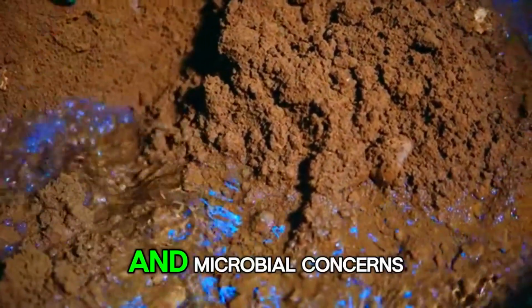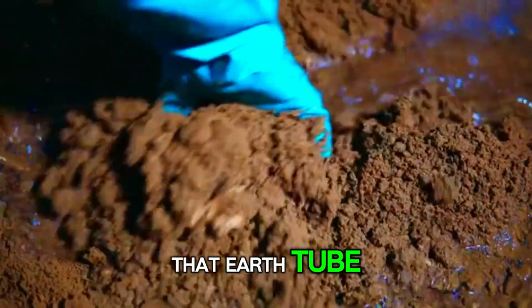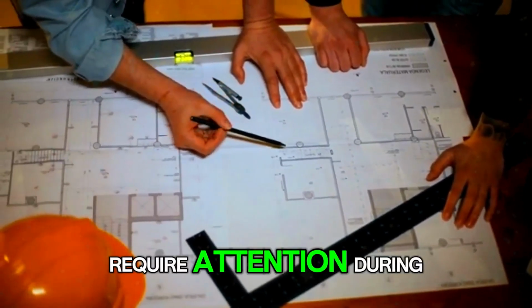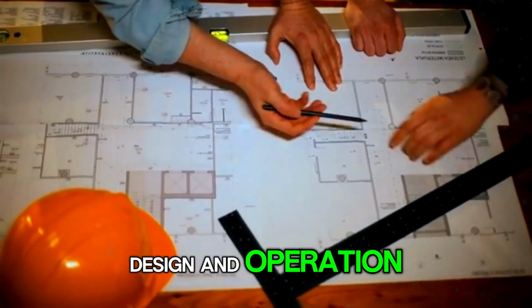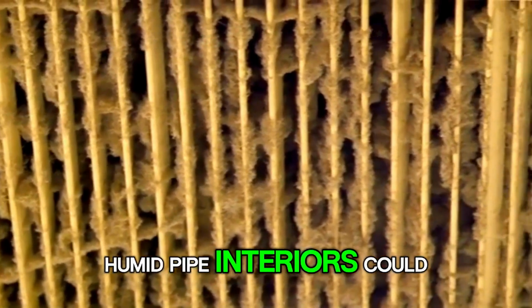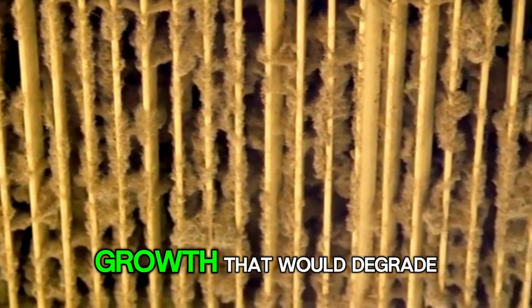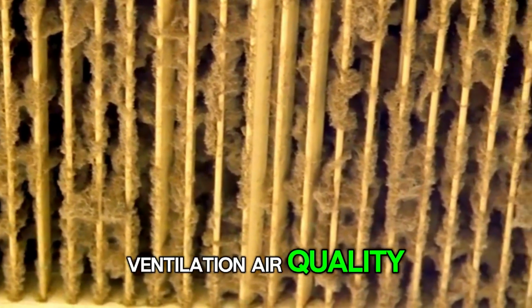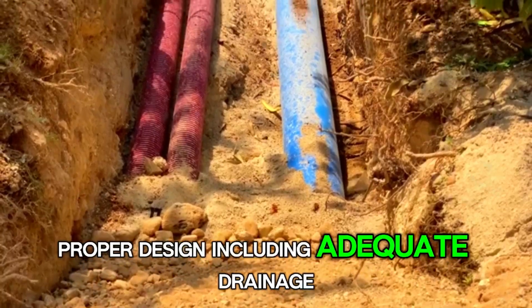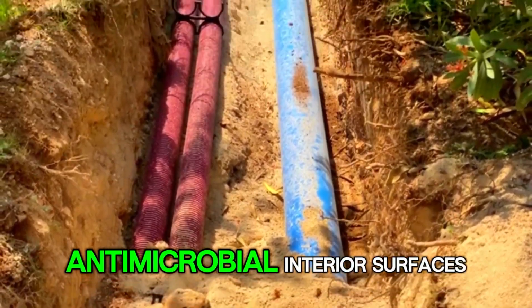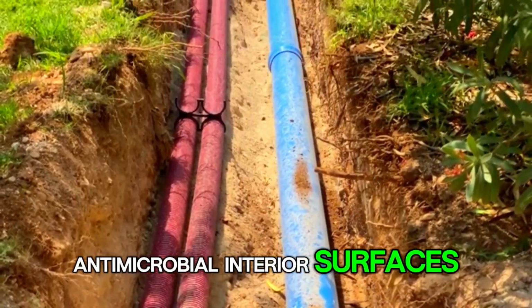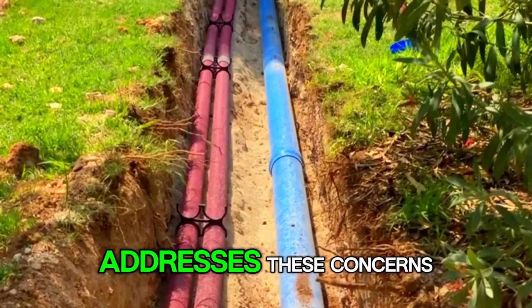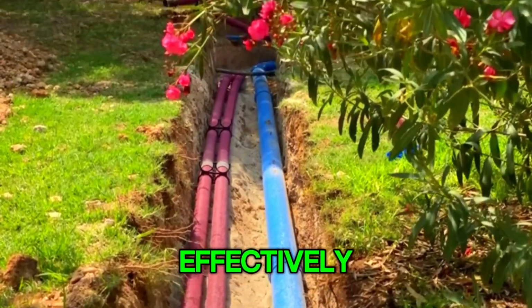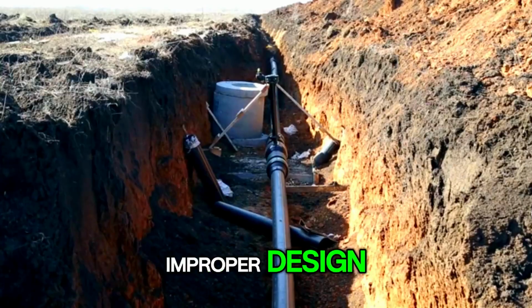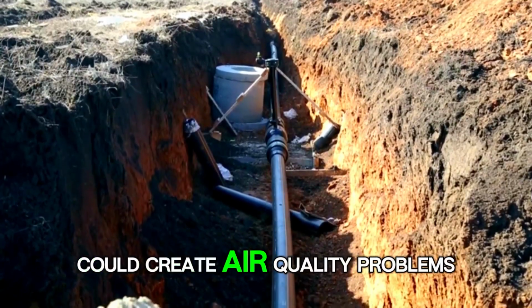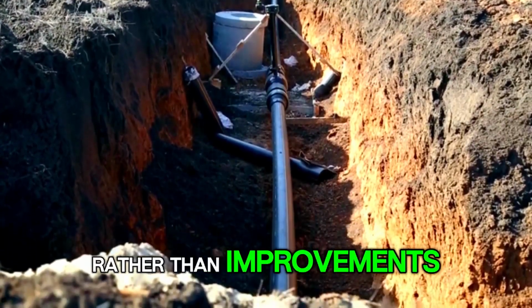Third, the moisture and microbial concerns that earth tube applications could create require attention during design and operation. Humid pipe interiors could potentially support microbial growth that would degrade ventilation air quality. Proper design, including adequate drainage, antimicrobial interior surfaces, and periodic cleaning provisions, addresses these concerns effectively. Improper design or neglected maintenance could create air quality problems rather than improvements.